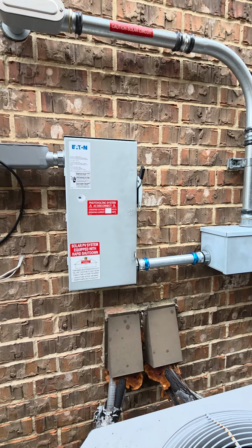Basically, what the AC sense disconnect does is when you turn off the grid, that third pole connects into the AC sense and shuts down the batteries and solar at the same time. I didn't want to pay $500 for a new 3-pole quick disconnect, so I utilized the 2-pole that I had.